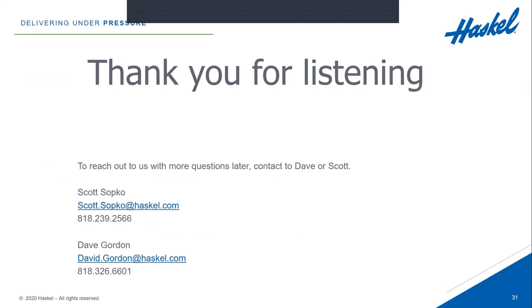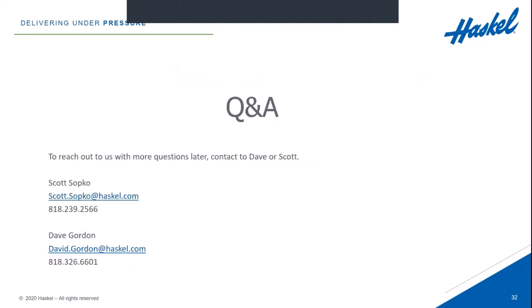We'll now look at some of the questions. Before I get to that, if you have any questions, please reach out to either myself or Scott Sopko — our emails and phone numbers are listed on the screen. A question came in: can the controls be set to modulate the media to control the triple phase of the media for better process controls? Rick's answer was that rate control will modulate the media, and temperature and pressure control can keep the gas in the phase desired. Another question: is the mechanical drive a planetary screw drive after the servomotor? It is actually a linear ball screw after the servomotor. Is the IoT functionality a third-party provided service? The remote monitoring is provided with every Q-Drive — you would just need to connect the drive to an internet connection to view the function remotely.